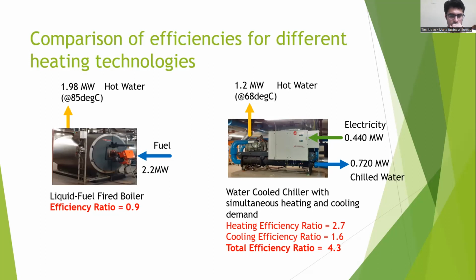Some may say that not all establishments, not all buildings, have a demand for both hot water and chilled water at the same time. Yet, I've seen heat pumps in Malta, even on big installations, though not as big as these. I've seen heat pumps in hotels about 12 years ago, basically operating the chiller in heating mode. They were getting the hot water, the heat, and dissipating the cold water. So even if you don't have a demand for both chilled and hot water, you're still running at an efficiency of 2.7 times as much. So it still pays off to operate a heat pump and not a boiler, considering also, as I said before, that you're not emitting any flue gases.